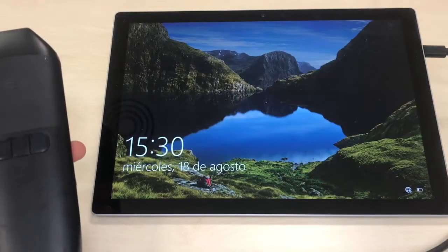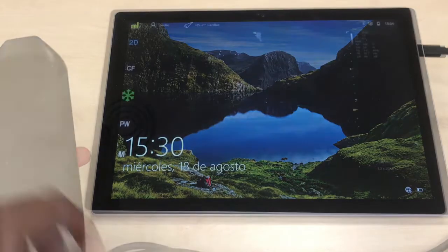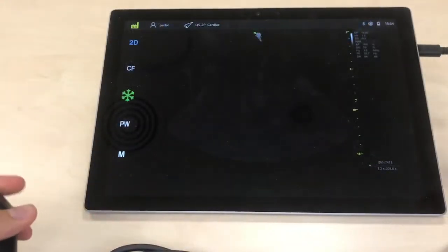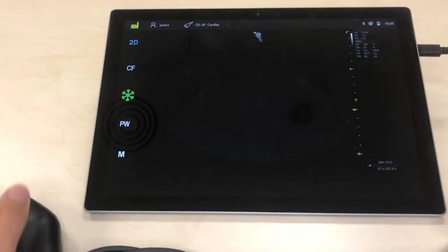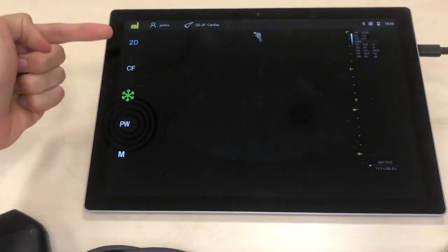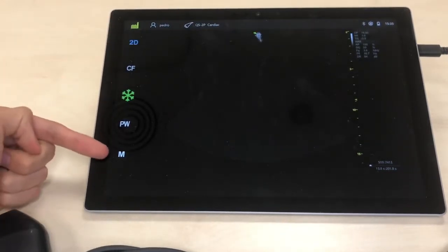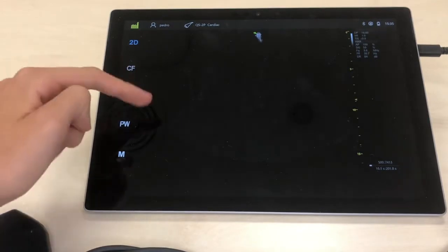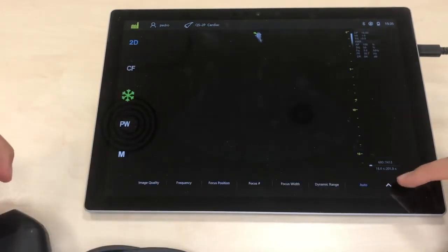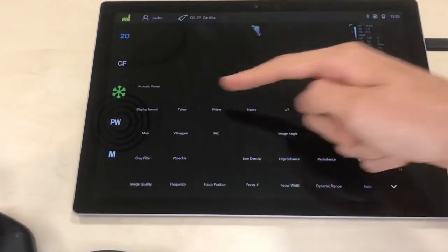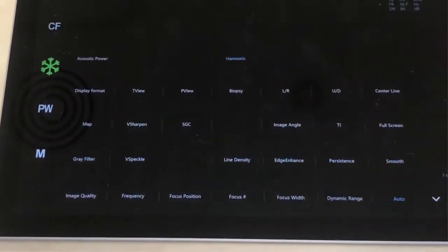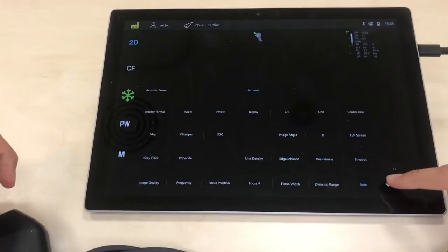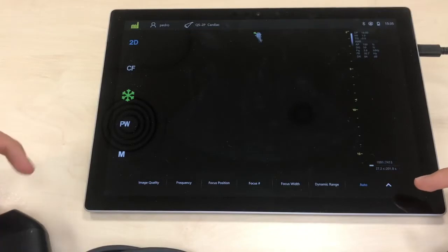The boot up time is usually less than 30 seconds. This is the main page of their app, and we can see it has quite a lot of features. On the left, we can choose the imaging mode between B mode, color Doppler, pulse wave Doppler, and M mode. On the bottom bar, we can find some advanced imaging settings, typical from advanced machines and not from pocket devices, so good point, Vinno. This device is the most similar to cardiology machines I have reviewed so far with regards to imaging settings.